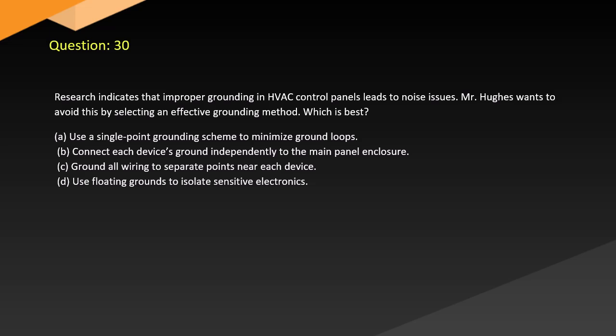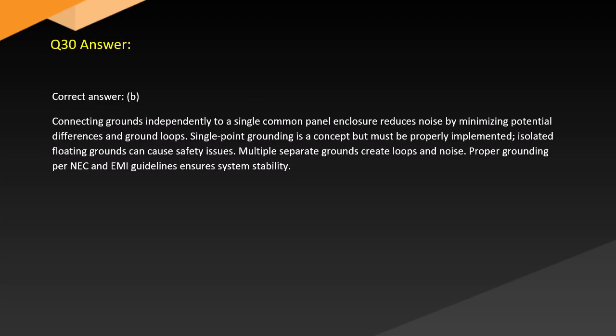Question 30. Research indicates that improper grounding in HVAC control panels leads to noise issues. Mr. Hughes wants to avoid this by selecting an effective grounding method. Which is best? A. Use a single-point grounding scheme to minimize ground loops. B. Connect each device's ground independently to the main panel enclosure. C. Ground all wiring to separate points near each device. D. Use floating grounds to isolate sensitive electronics.